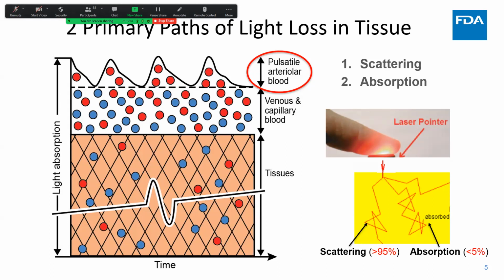Now, the light as it enters and ultimately exits is lost by two primary methods. About 95% of it is lost to just scattering. It goes all over the place, and the more it's exposed to fat or especially air, the more likely that scattering is going to occur. And then the other component is absorption. Absorption is based upon other materials that will hold that light for a while and reduce its intensity before it comes back out to the surface where it can be measured.